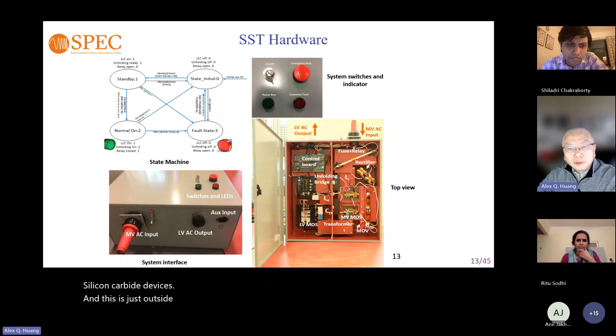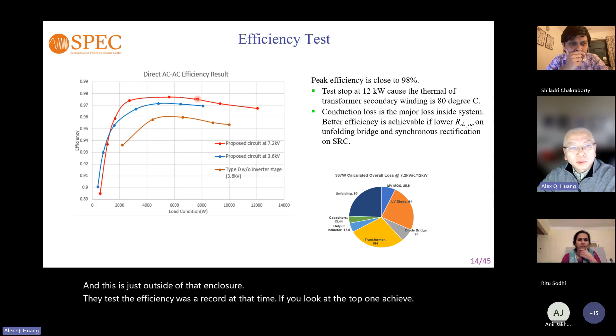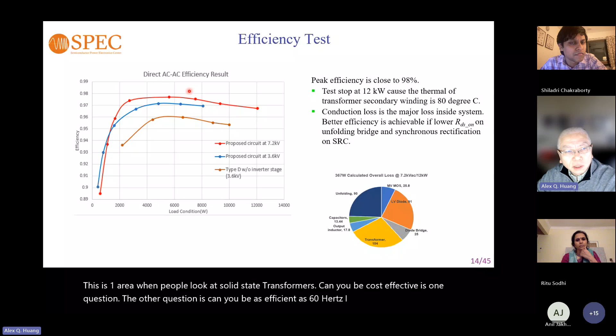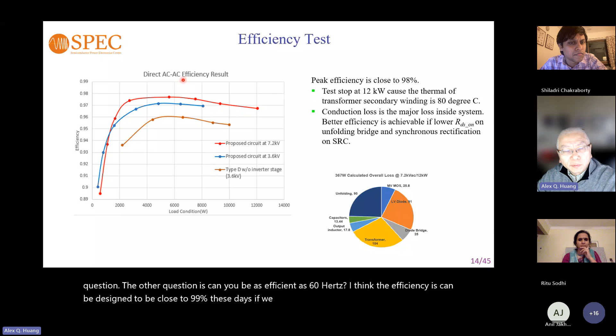The tested efficiency was a world record at the time—if you look at the top one, it achieves almost close to 98% efficiency. One area people look at with solid state transformers is: can you be cost effective? The other question is: can you be as efficient as 60 hertz? I think the efficiency can be designed to be close to 99% these days. If we do this again, we can probably go up to 99%. So efficiency really matches the line frequency transformer.